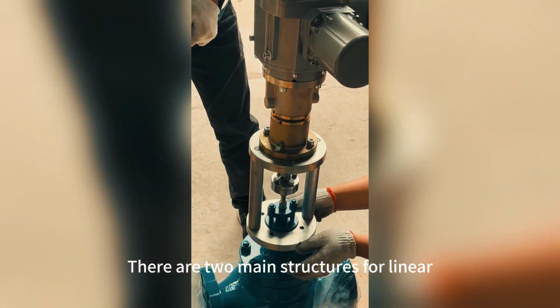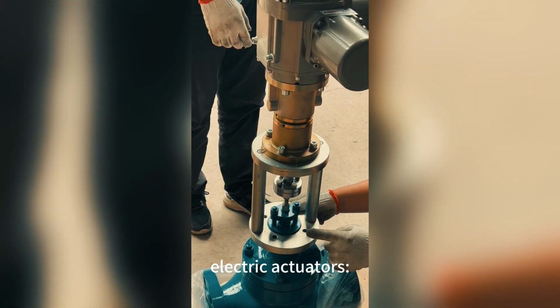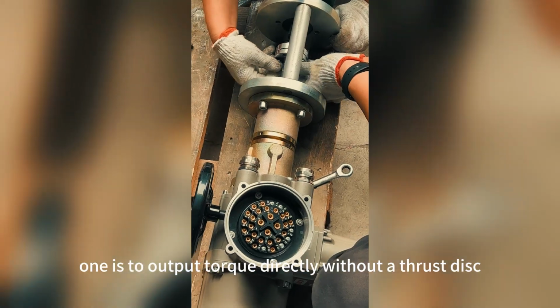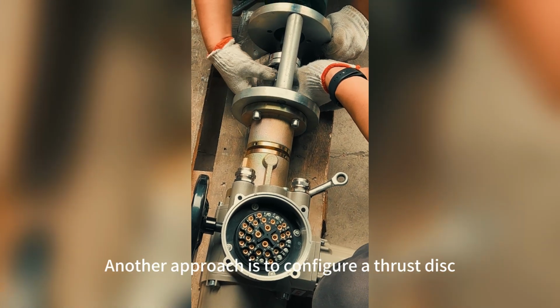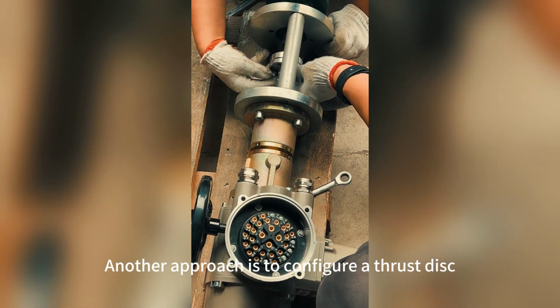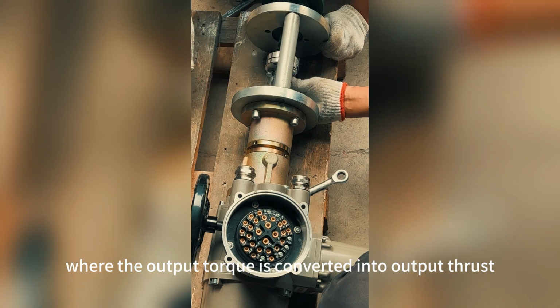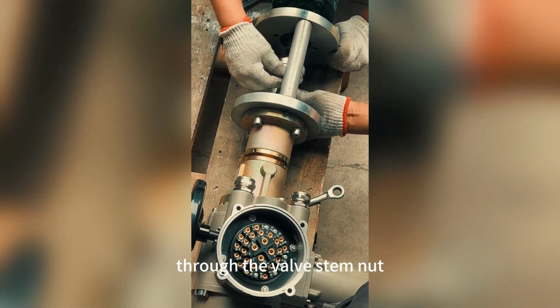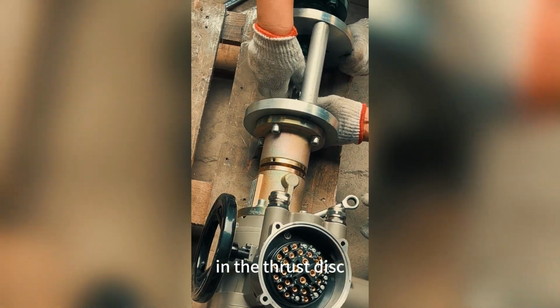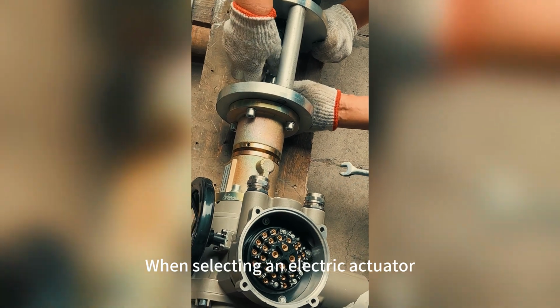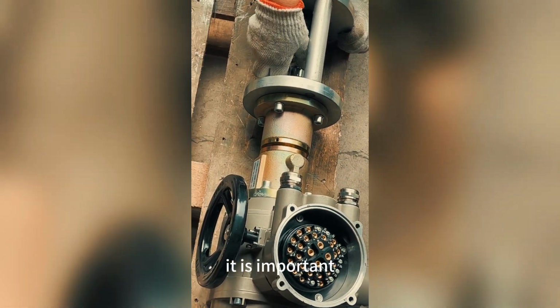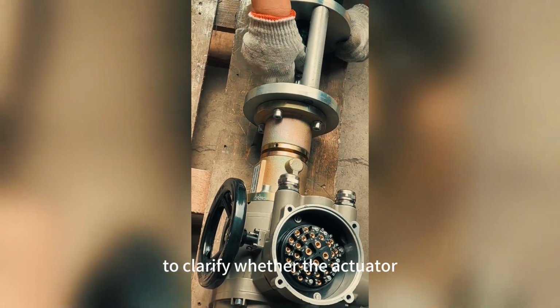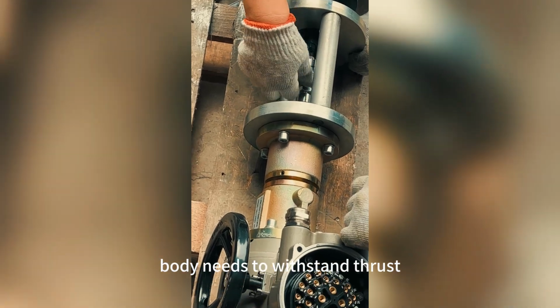There are two main structures for linear electric actuators. One is to output torque directly without a thrust disc. Another approach is to configure a thrust disc, where the output torque is converted into output thrust through the valve stem nut in the thrust disc. When selecting an electric actuator, it is important to clarify whether the actuator body needs to withstand thrust.